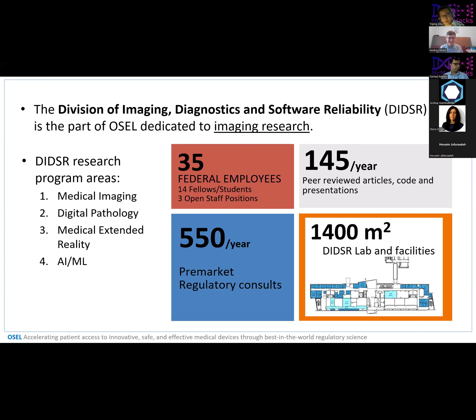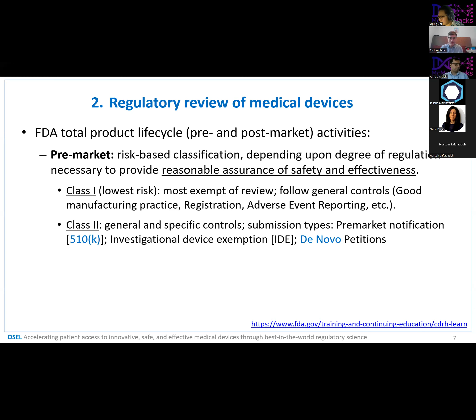So how does the FDA review medical devices? We use a total life cycle approach with pre- and post-market activities. The pre-market process is based on a classification depending on risk, and the manufacturers have to show a reasonable assurance of safety and effectiveness of the devices. The devices are stratified in 3 classes. The lowest risk is class 1. This is mostly exempt from evaluation and has to follow just some general controls. Class 2 are moderate-risk devices where there is some need for specific controls. These are the applications I will talk more about later, the pre-market notifications and de novos. Finally, higher-risk devices or devices that have no predicate in the market require pre-market approval, which is a more stringent process.